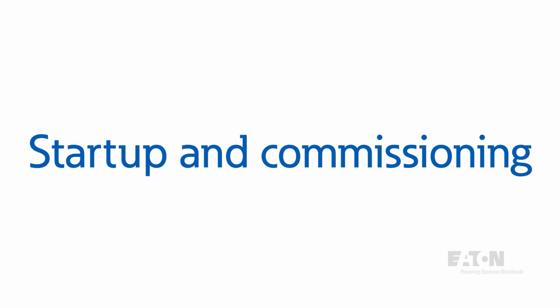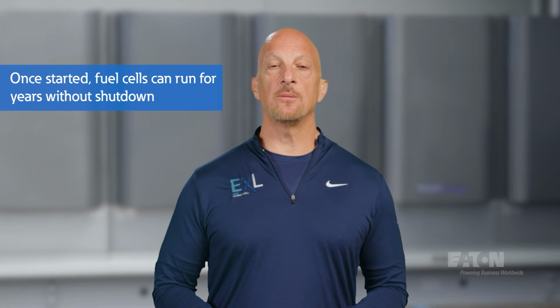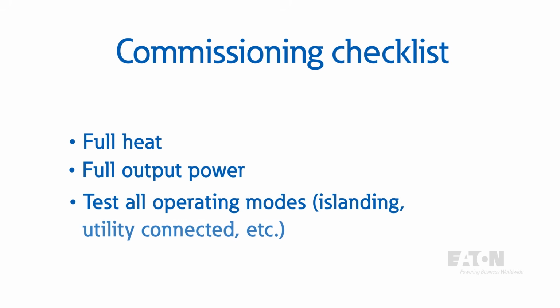Fuel cells take time to come up to full heat for operational modes, and this can take 12 to 48 hours. So planning the initial startup, commissioning, and operation is critical. But once they're operating, they're intended to stay on for years. In our case, during commissioning, we ran the unit up to full heat, then tested it with the full 50 kilowatt output power. Next, we tested all of the operating cases, including islanding, and then finalized the commissioning, and the unit has been running ever since.